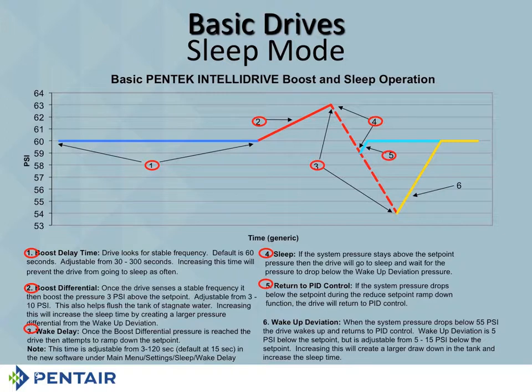Again, you can see it's adjustable, all right? Number 6 says, okay, we've gone to sleep, and now we've got to drop all the way down to 5 psi below our set point before we're going to turn back on, okay? And that's our wake-up deviation. So you've got a 9-pound differential in that system, which is good because it gives you a chance to move the water through the tank.